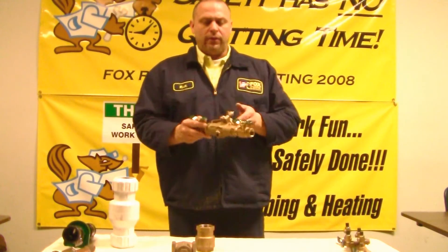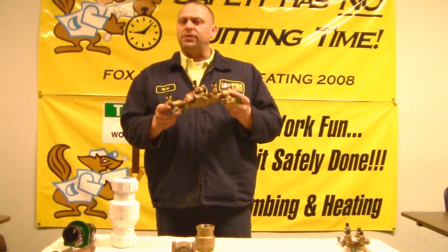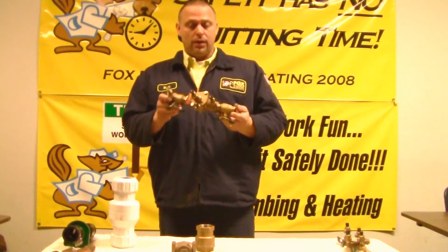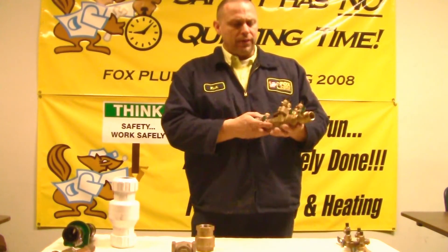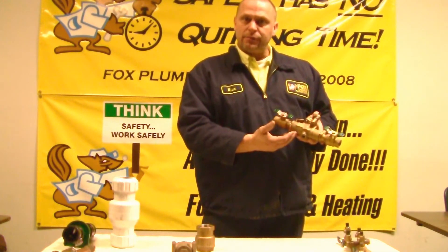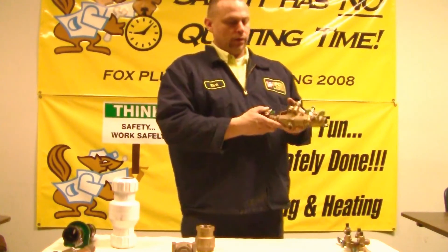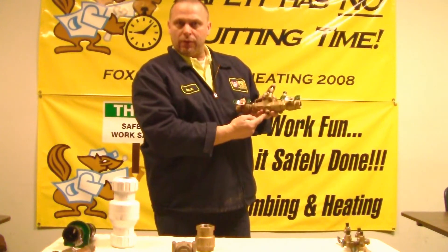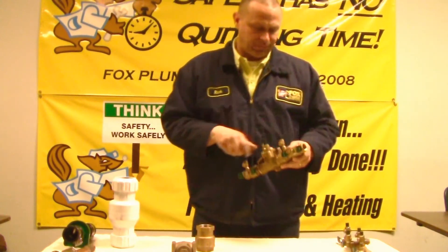What I have right here is called an RP device — it stands for reduced pressure principle. You've probably come across these a bunch of times and didn't even know it. Every time you go to a fast food restaurant and get a drink, these are placed on soda fountains to separate the water from getting contaminated. These are also used for boiler systems and heating systems in the home to keep the heated water separate from your potable drinking water. These also have test ports that have to be tested yearly, and there's a relief drain on the bottom which goes to a drain. These are used inside homes and also in commercial applications.